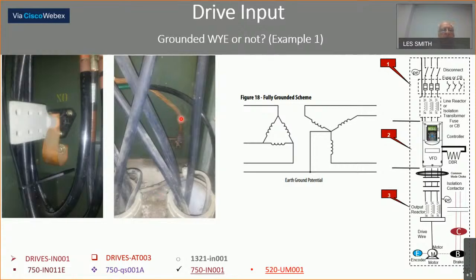Here's where the customer actually ran the ground. He brought all the grounds back, butt spliced them together right here, and then 4 foot away from the XO, he tied that to ground. I blessed it and said, yes, it's grounded. I've actually had second thoughts since then. If we're balanced, we shouldn't have much current here. But if we're not, we may have a little bit more current here than what this joint can handle. I might change my mind today and say ungrounded, and I would pull out the resistor or the jumpers on that. So that's the first example.